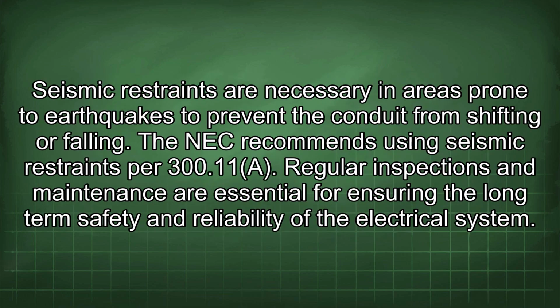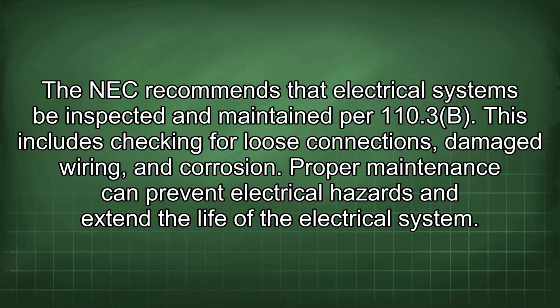Seismic restraints are necessary in areas prone to earthquakes to prevent the conduit from shifting or falling. The NEC recommends using seismic restraints per 300.11(A). Regular inspections and maintenance are essential for ensuring the long-term safety and reliability of the electrical system. The NEC recommends that electrical systems be inspected and maintained per 110.3(B). This includes checking for loose connections, damaged wiring, and corrosion. Proper maintenance can prevent electrical hazards and extend the life of the electrical system.